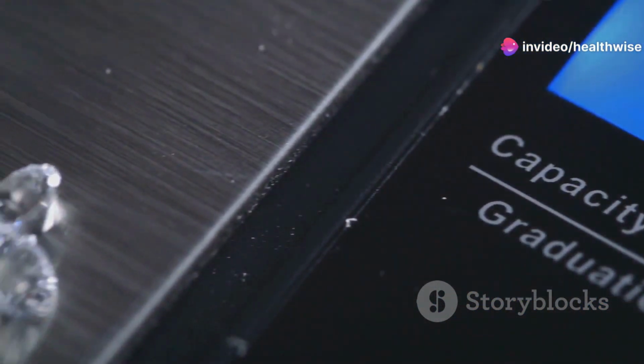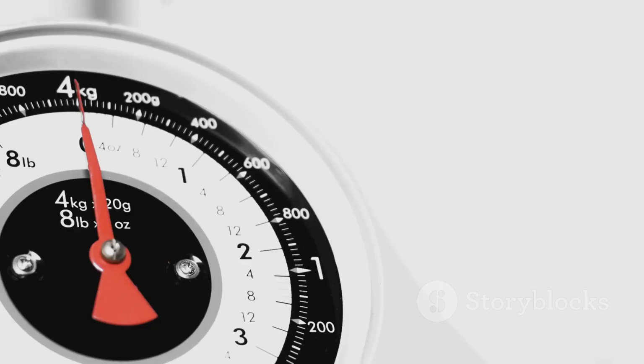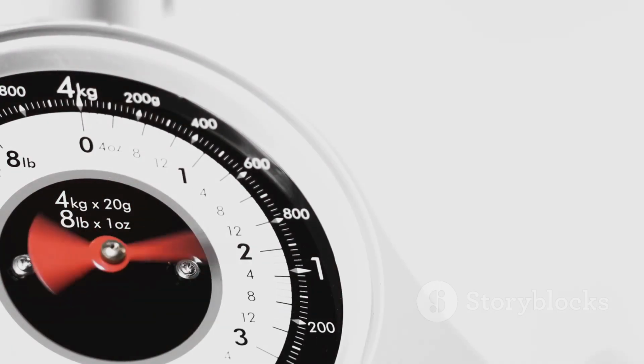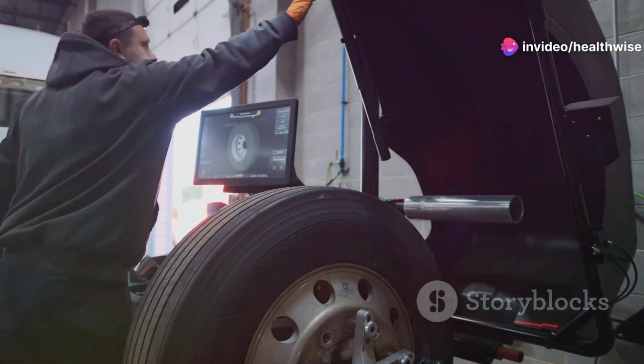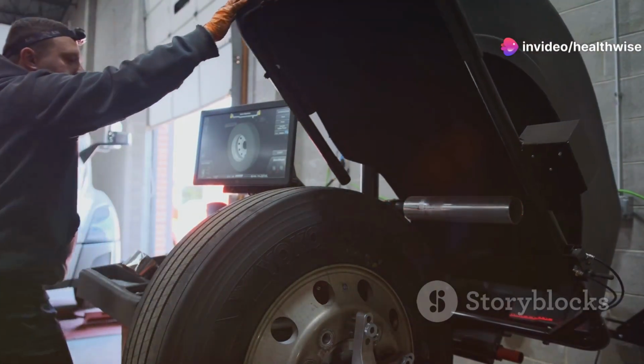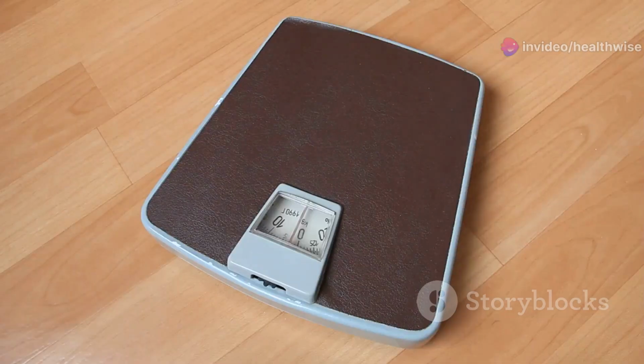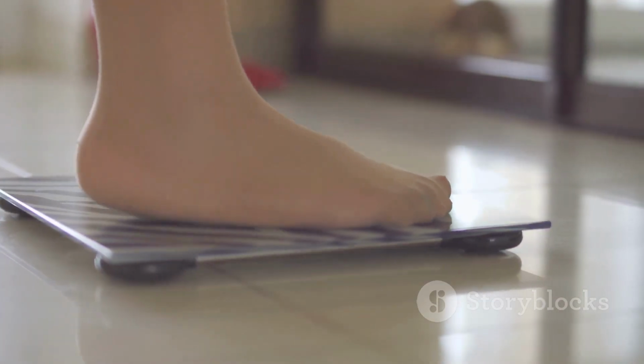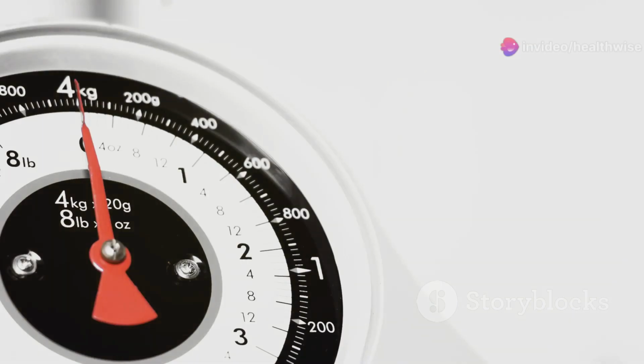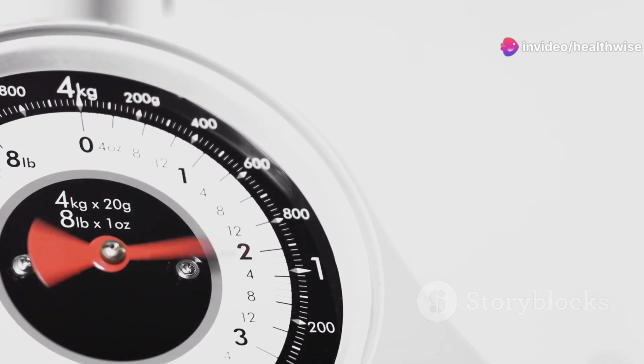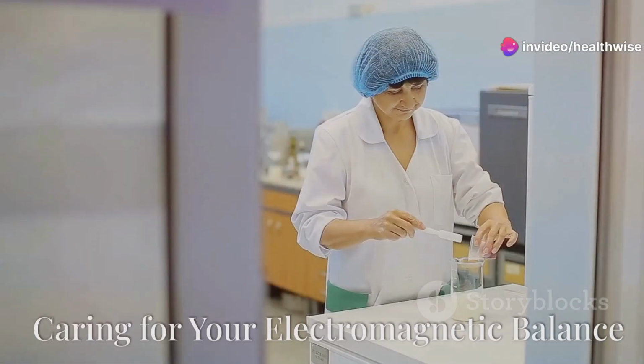To calibrate your balance, start by ensuring it's clean and level. Then, following the manufacturer's instructions, place the appropriate calibration weight on the weighing pan. The balance will then adjust its internal settings to align its reading with the known weight. Regular calibration is crucial, especially after moving the balance, experiencing significant temperature fluctuations, or suspecting any impact or vibration that might have affected its accuracy. By performing this simple yet essential ritual, you ensure that your balance remains a reliable tool for precise measurements.